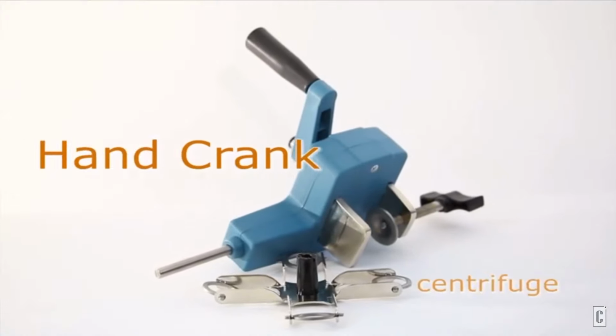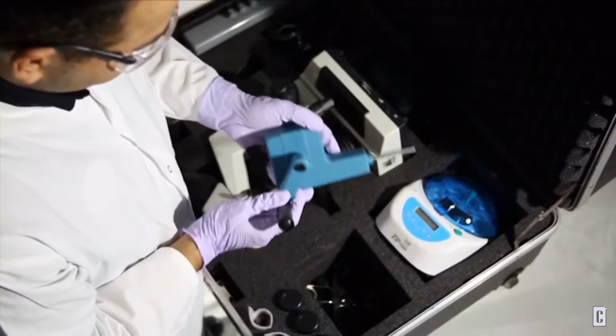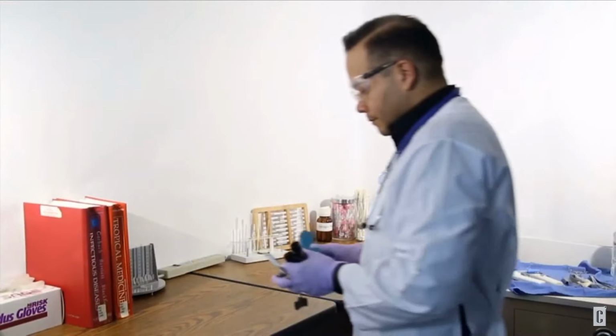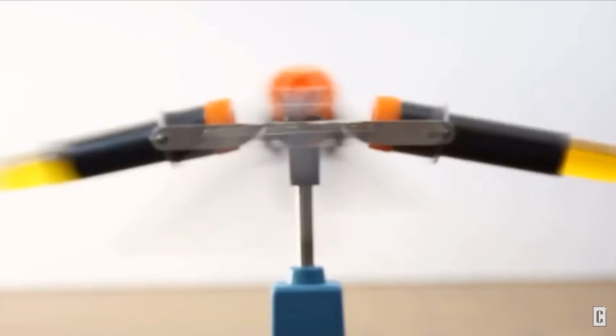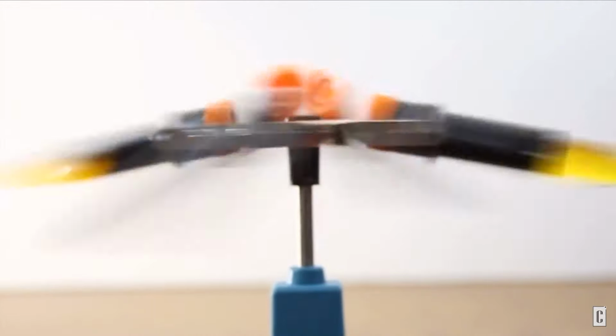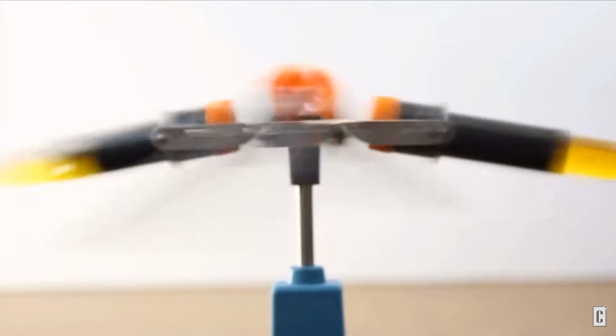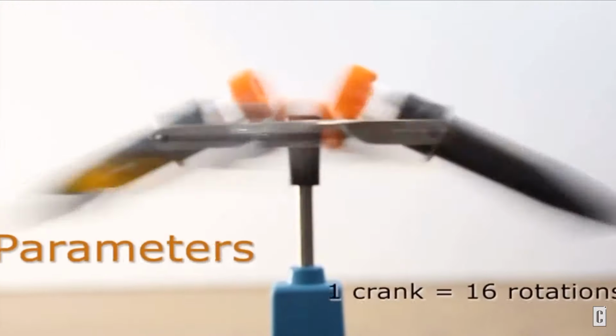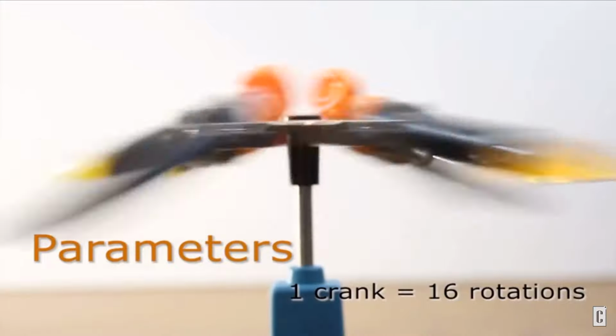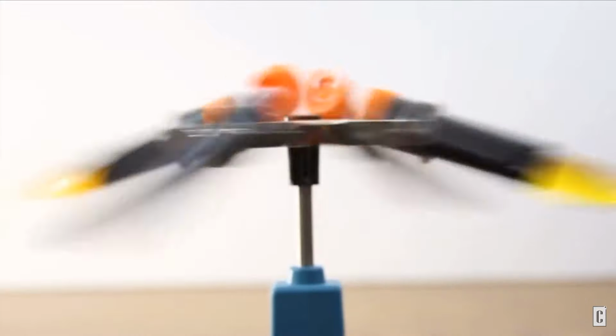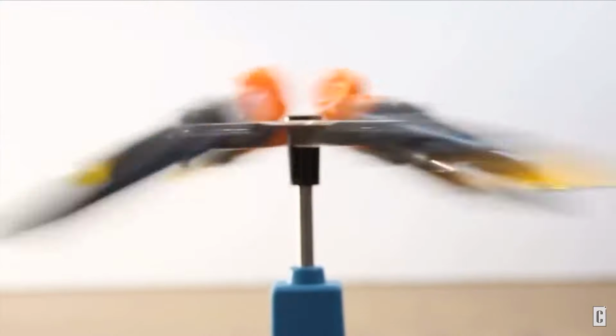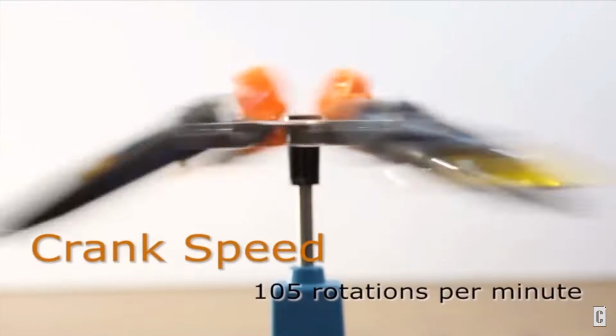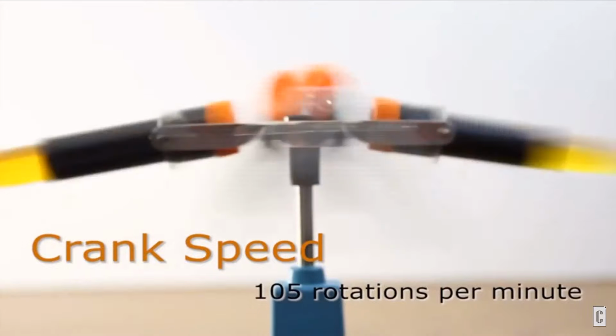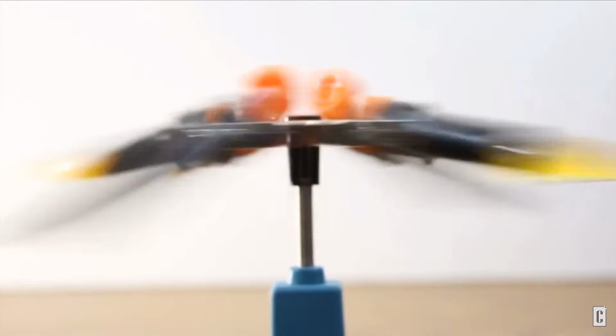Hand crank centrifuge. The hand crank centrifuge spins liquids up to 15 milliliters, such as urine and blood, and is operated by hand. The important factor when separating substances by centrifugation is the amount of force needed for separation without damaging the substances. Refer to the instruction manual for the amount of force and formula for calculation. To obtain a proper relative centrifugal force, the centrifuge must be cranked at 105 turns per minute to achieve a tube revolution per minute of 1,692.